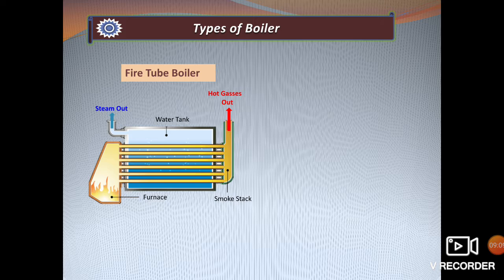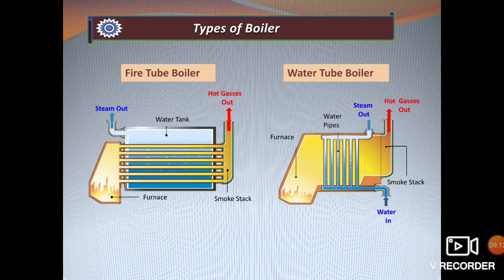The water tube boiler has a design fairly similar to a fire tube boiler, but instead of the furnace heating fire tubes, it heats water tubes inside the furnace. When the water is boiled, steam is generated and taken out for use. Water tube boilers are more thermally efficient than fire tube boilers, but they are more complex to construct, and water quality can be an important factor — the water may need filtering to operate more efficiently.